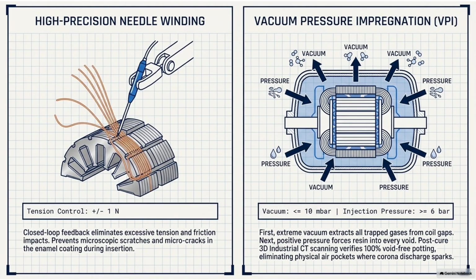The validation metric for this wire is incredibly stringent. It must maintain a partial discharge inception voltage, a PDIV, of at least 1.5 times the maximum system bus voltage, even while continuously operating at 150 degrees Celsius. So they demand a 50% safety margin under the absolute worst-case thermal conditions. That's serious armoring. And the stator slot itself gets a multi-layer fortress too, right? Using NMN insulation paper. Yeah, NMN stands for Nomex Mylar Nomex. When they insert the coiled wires into the grounded iron core, they don't rely solely on the wire enamel. They line the slots with this 3-layer composite. Okay. The Mylar in the center provides exceptional dielectric strength to block current leakage, while the outer layers of Nomex, which is the same aramid fiber used in firefighter gear, provide thermal stability and mechanical protection against vibration. Oh, wow. Firefighter gear in the motor.